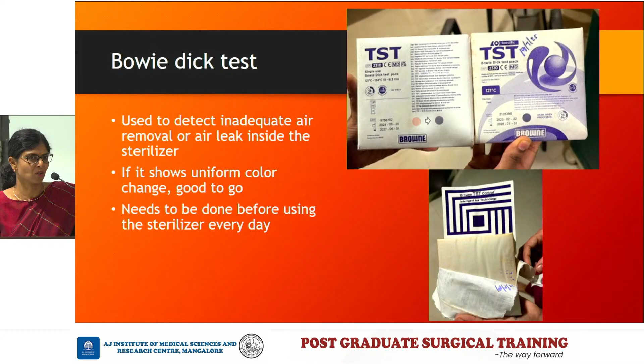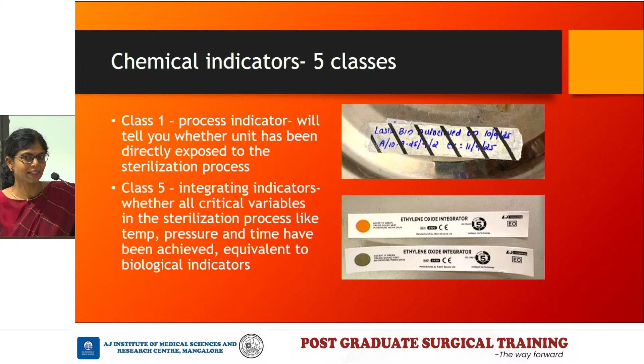It will only tell you whether the unit has been exposed to the sterilization process, nothing else. Whereas a class 5 indicator will tell you whether all the variables like temperature, pressure, time have been achieved, and they can be counted equivalent to biological indicators which are the gold standard of sterilization. So this is a class 1 indicator. You can see on the top picture that it is not yet done, and then there is a color change down, so it is done.